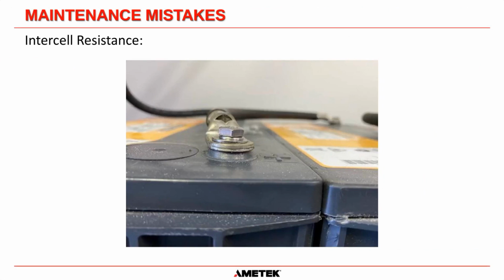What you need to do, so here's another example. This is on a valve-regulated lead-acid battery. Many people would put their clamp on this here, or they may even go back onto the terminal barrel here, to get the resistance. And that, once again, doesn't give you any information whatsoever. To get it, your clamp would have to go on this bottom post here and on the bottom post here. And that clamp cannot touch this portion of the lug, because as soon as it touches that, you are not getting the surface connection resistance. And that's what we're trying to find out when we do intercell resistance measurements.